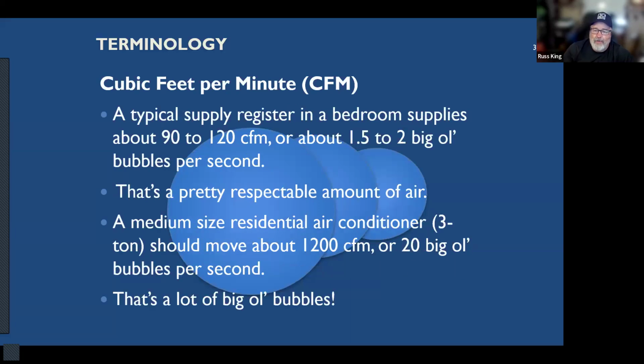A typical supply register is 90 to 120, so that'd be 1.5 to 2 big old bubbles per second. So 2 bubbles every second. 1001, 1002, all these bubbles. So now it's substantially more, twice as many as 60 CFM to get 120. That's a pretty good amount of air starting to come out of there.